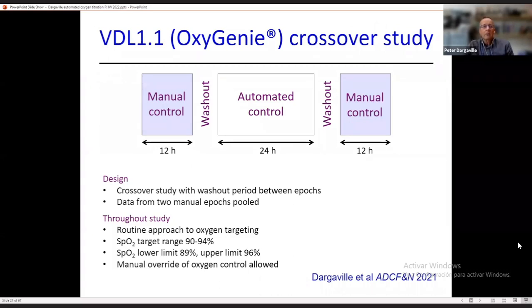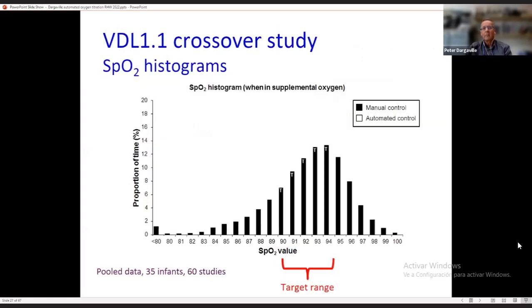Our study is not included in the Cochrane review because it wasn't a randomised crossover study. We instead chose a design of having a 24-hour period of automated control nested between 2 12-hour manual control periods with a washout of 30 minutes. And throughout the study, we asked our staff to take a routine approach to oxygen targeting with an SpO2 target range of 90 to 94%, with alarms at 89 and 96, and manual override of the controller allowed by the staff at any time.